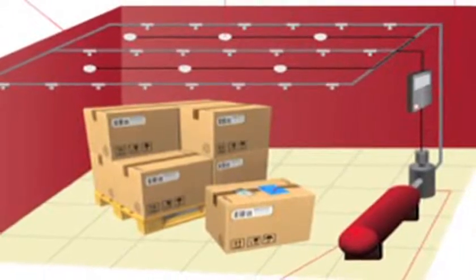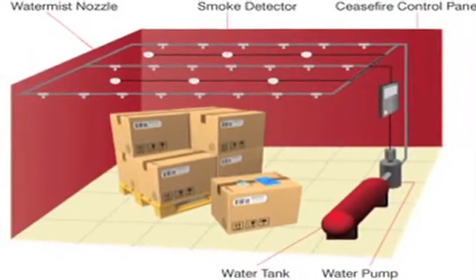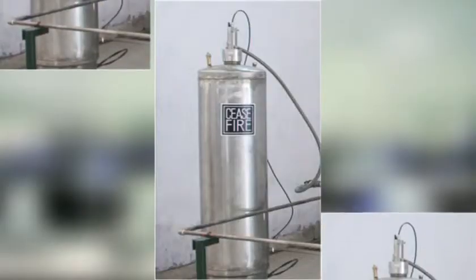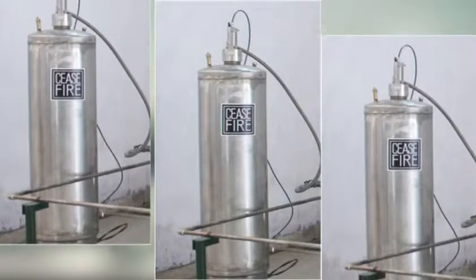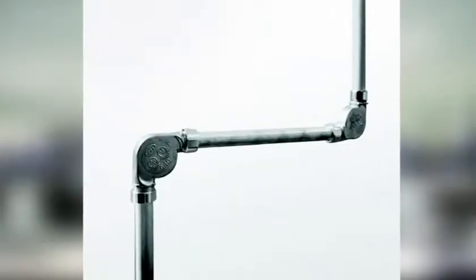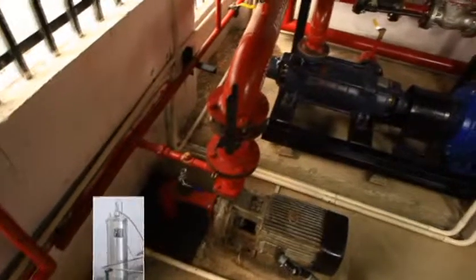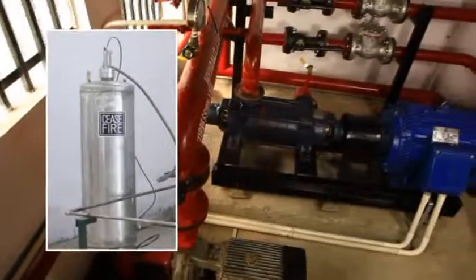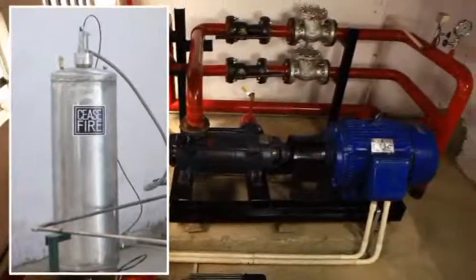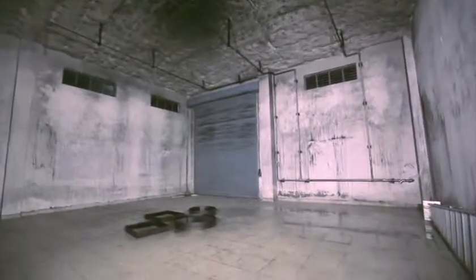There is also a pulse mist system that's been specially designed for smaller environments or for areas where the fire hazard is likely to be in a smaller enclosed space. The water source in the case of the pulse mist system is a pressurized cylinder available in sizes ranging from 12 liters to 100 liters, connected to the system via a manifold. The pulse mist system is just as effective as the pump-driven system, the only difference being that it's designed for smaller applications. Now, let's see how the indoor auto-quell pulse mist system works in real life. As soon as it detects the fire, the Ceasefire Water Mist indoor auto-quell system starts up and puts out the fire in just a few minutes.